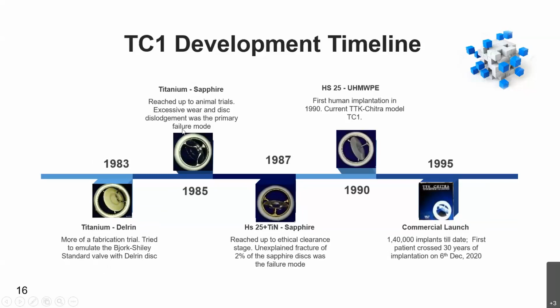By 1985, we had the first of our own device, which had a titanium cage. In fact, the valves have three components. One component is the cage or a frame, a metallic frame, which is used as an anchor for the disc or a tilting disc. And the tilting disc acts as the opening and closing mechanism in the valve. Then the entire device is stitched onto the muscles of the heart using a fabric ring, which is expected to get interfaced with the tissue, and slowly tissue will grow into the fabric and form a nice joint. That is what is expected of this polyester fabric.